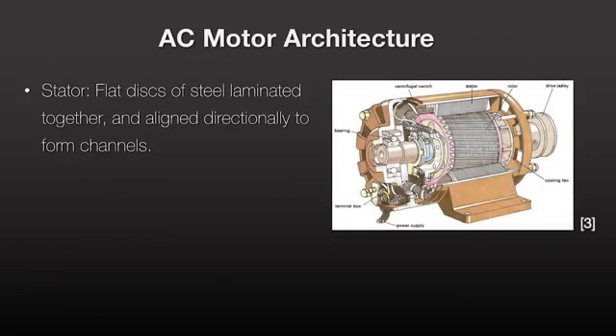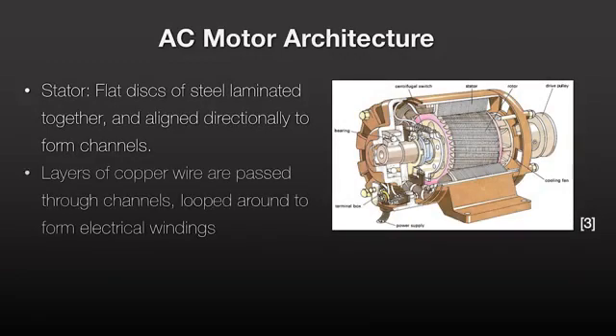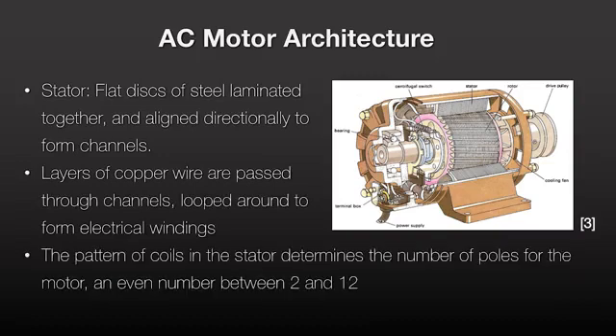The stator consists of a series of flat steel discs laminated together. They are aligned directionally to form channels for the stator windings. These windings consist of layers of copper wire, which when passed through the channels create loops to form an electromagnet. The pattern of coil windings in the stator determines the number of poles for the motor, an even number usually between 2 and 12.